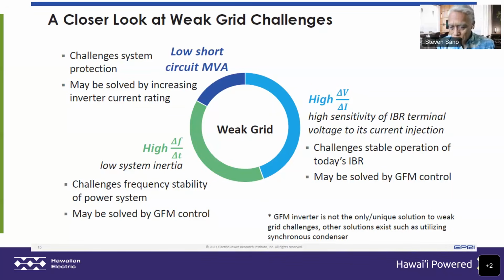This next slide I borrowed from EPRI because it is a very good slide. When we talk about weak grids, I think a lot of times people have this false conception that we're just talking about lower fault currents. That is part of the picture, but not a complete picture. We do have lower fault currents, and they behave differently, which is an issue. We do have impacts to voltage, so high dV/dI type characteristics. We have impacts to frequency where there is high df/dt characteristics. And you'll see on this particular slide mention of GFM, grid forming inverters. Grid forming inverters look like they have a very good potential to address some of the issues that we're seeing, but we'll talk about that a little bit later.